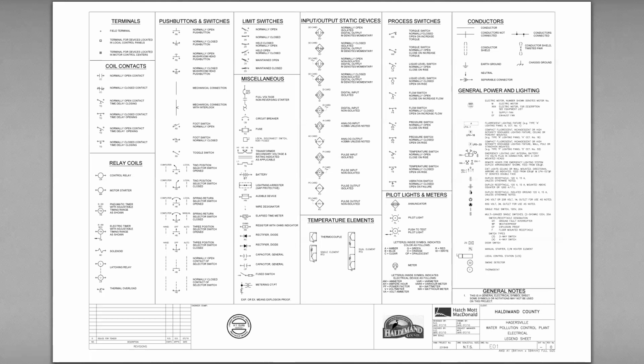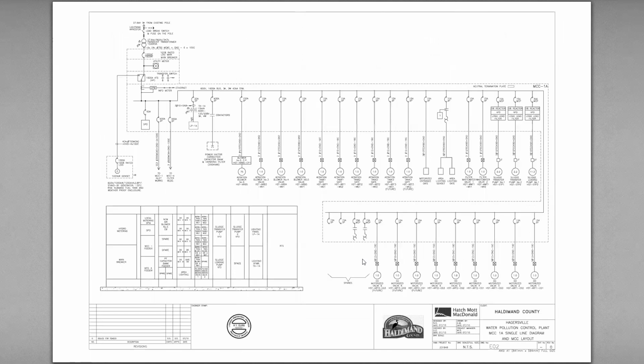So another client, this is a sewage treatment plant. Here's their legend for this drawing set, showing the different terminal blocks they're using, the coil and contact examples, latching coils, your push buttons and switches, different temperature elements, input outputs, and then different electrical drawings, electrical circuits. This drawing set is more encompassing than just a control panel. This is another thing that you'll see a lot. Sometimes the control drawings are embedded in larger drawing sets.